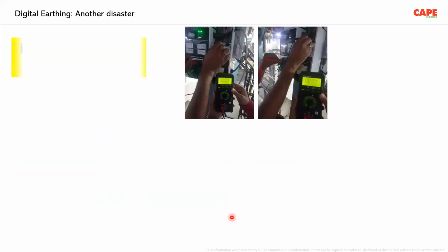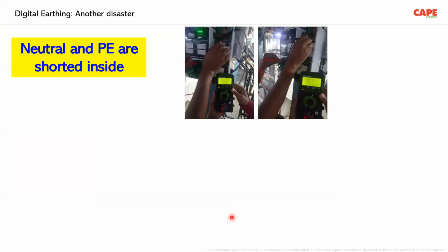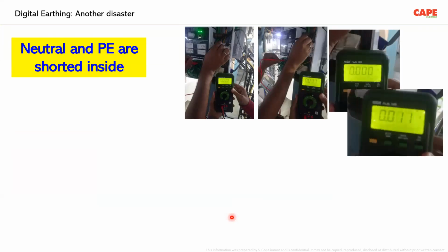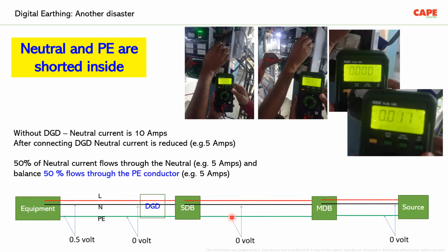And what we did is I checked the resistance between the neutral and earth. Actually, they are shorting the neutral and earth. The neutral and earth is simply short circuited. So in this particular case, without this digital disaster, neutral current is about 10 amperes. After connecting the digital disaster, neutral current is reduced to 5 amps because 50% of the neutral current flows through the neutral wire and the balance 50% goes through the earth wire.